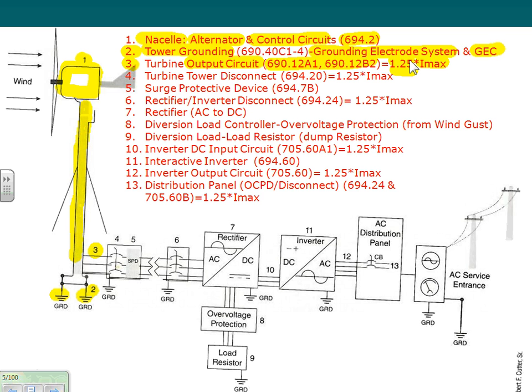With electricians, especially? Straightforward. The maximum multiplied by 1.25, and then 310.15(B)(16). You go get the conductor, and we came up with 4 AWG. How many 4 ARC? 3 of 4 AWG for the 3-phase. If it has a neutral, at this size I usually pull a full neutral, so 4 conductors of 4 AWG. And you size an equipment grounding conductor with it based on the overcurrent device that we're going to be talking about here. So if it's 3-phase, you will end up with a 5 conductor cable, or 5 conductors in a conduit. So that's number 3.